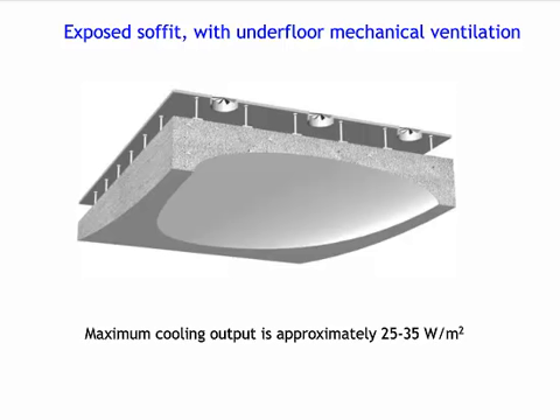But from a building physics point of view, there's the added bonus that it increases the surface area of the soffit, so you can get more heat in and out of the concrete and work the thermal mass a bit harder. If you combine that with underfloor ventilation, which you can see here, you've effectively doubled the surface area through which you can get heat in and out. So you can use depths of concrete, sort of 300-400 millimeters.